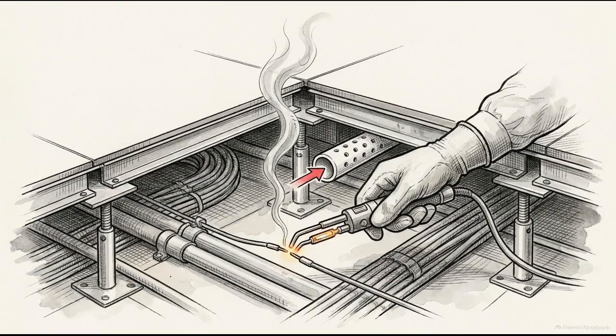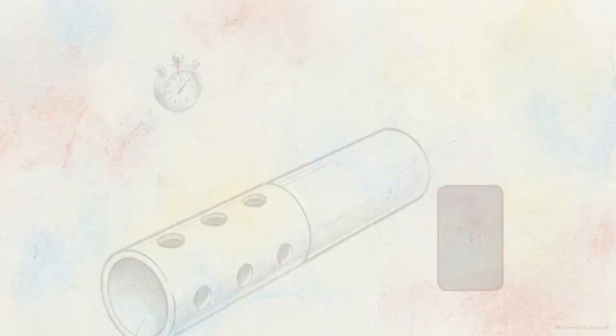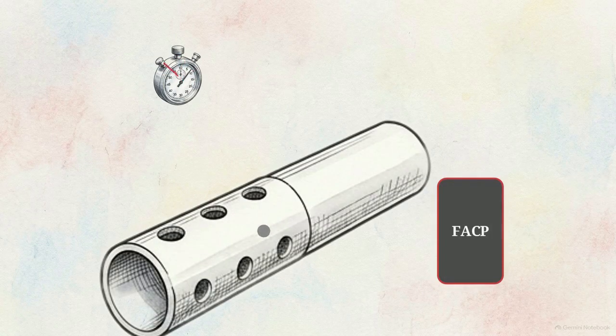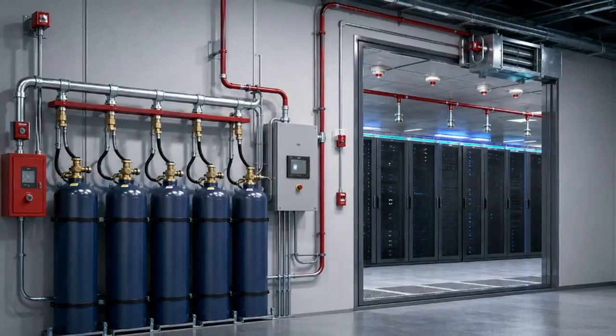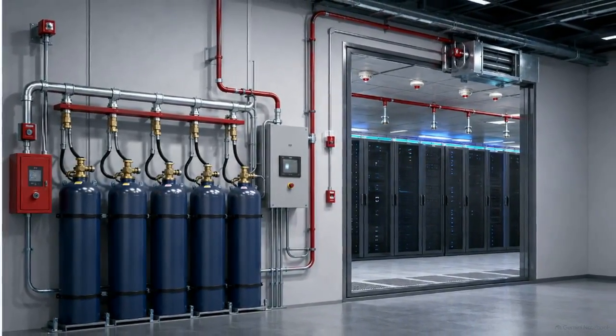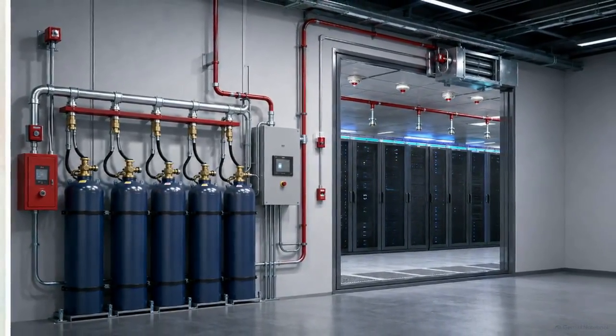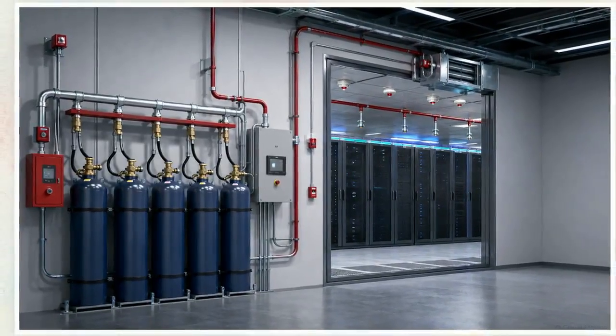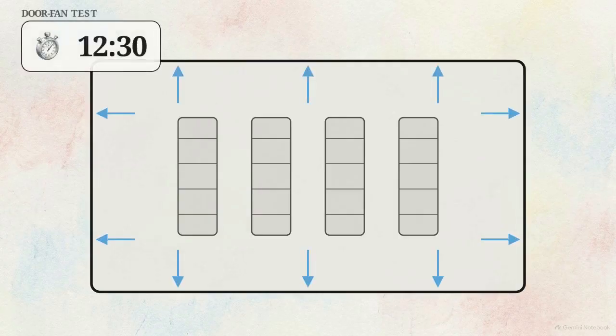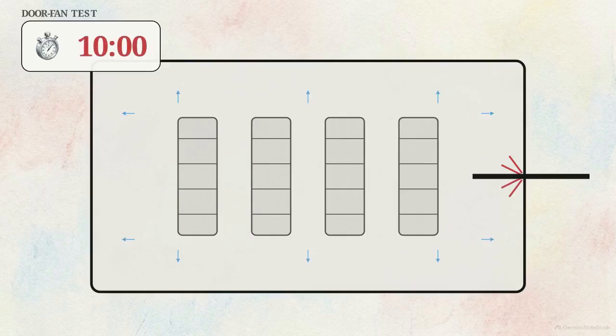Technicians measure transport times using an approved wire burn test below the floor tiles. This proves that smoke will travel through the sampling pipes and trigger the panel within strict code-mandated time limits. Special hazards, such as this clean agent manifold, require integrated testing. The cylinders, the room's structural integrity, and the releasing logic are interdependent. During a door fan test, if the hall holds pressure for only 12.5 minutes against a 10-minute requirement, that margin leaves no room for future structural shifts.